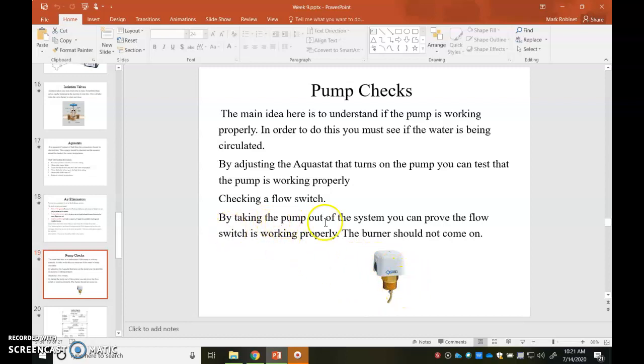In different scenarios, taking the pump out of the system can prove the flow switch is working properly and the burner should not come on. So in almost all scenarios, the burner should only come on if the pump is running. Most high efficiency boilers have built-in flow valves that check that the pump is running, and they will not allow the boiler to fire. If it did, you basically just would turn all that water to steam.